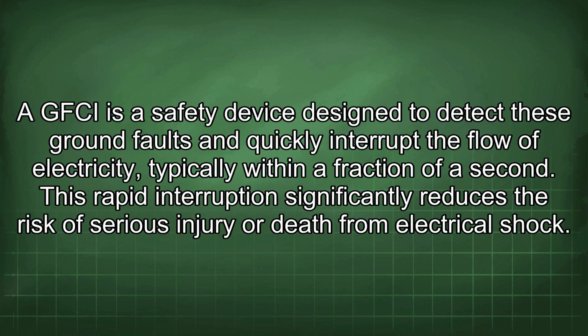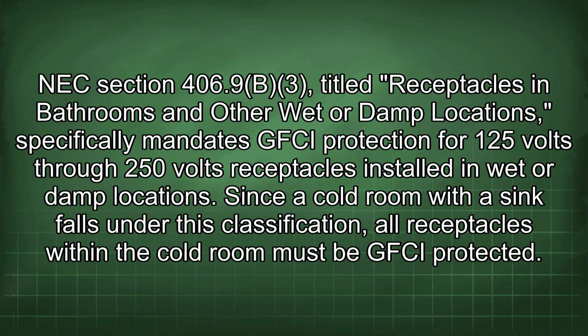A GFCI is a safety device designed to detect these ground faults and quickly interrupt the flow of electricity, typically within a fraction of a second. This rapid interruption significantly reduces the risk of serious injury or death from electrical shock. NEC Section 406.9(B)(3), titled Receptacles in Bathrooms and Other Wet or Damp Locations, specifically mandates GFCI protection for 125 volt through 250 volt receptacles installed in wet or damp locations.